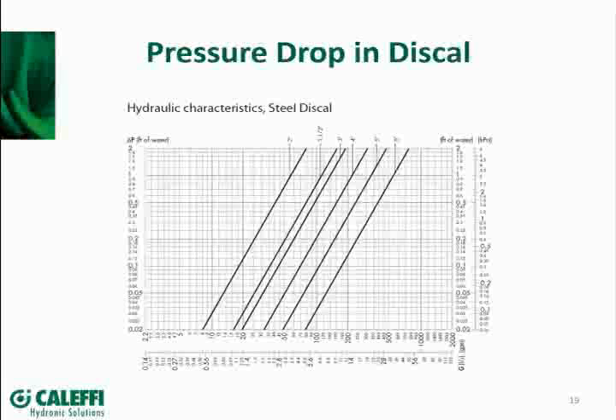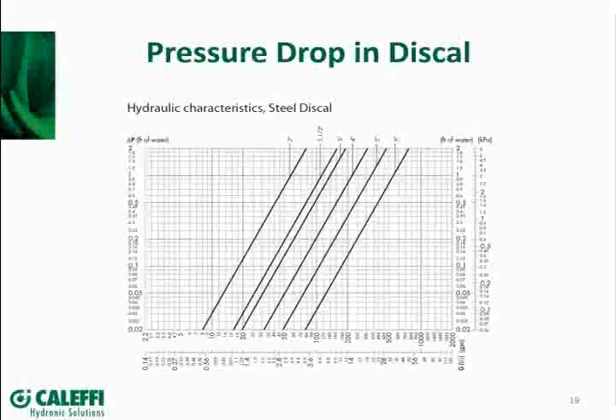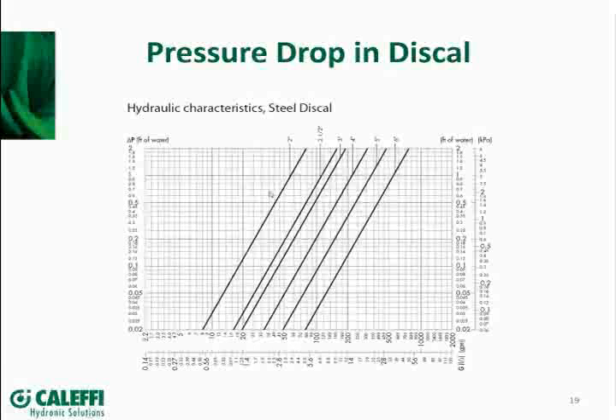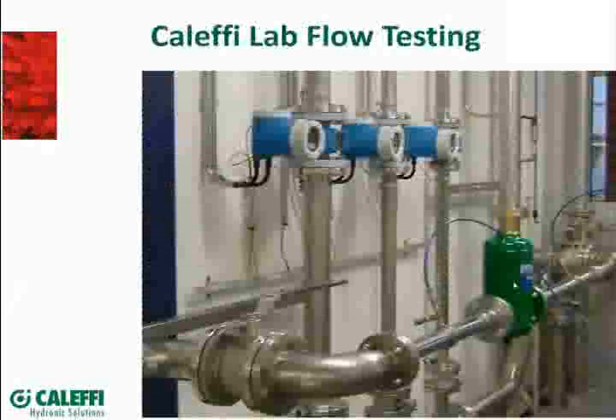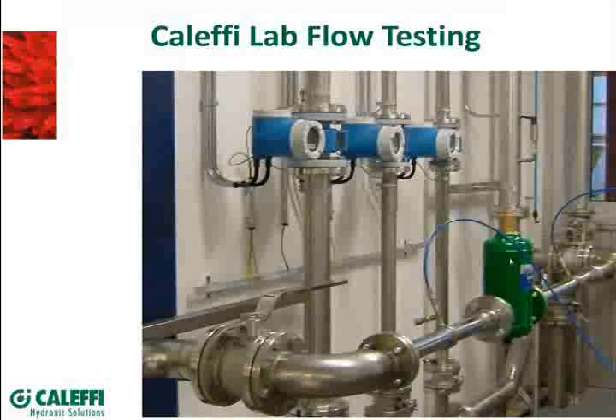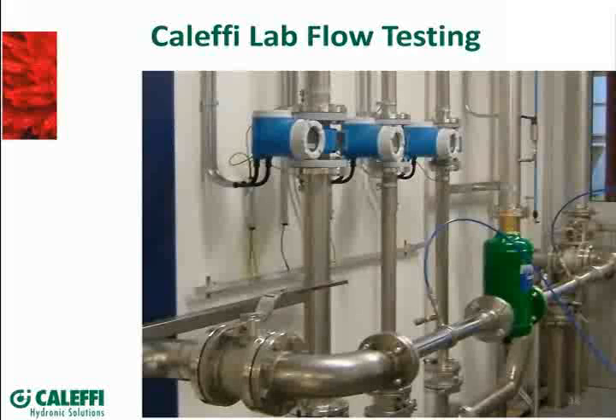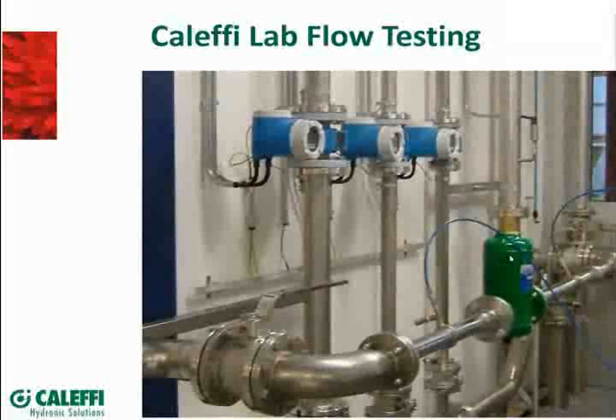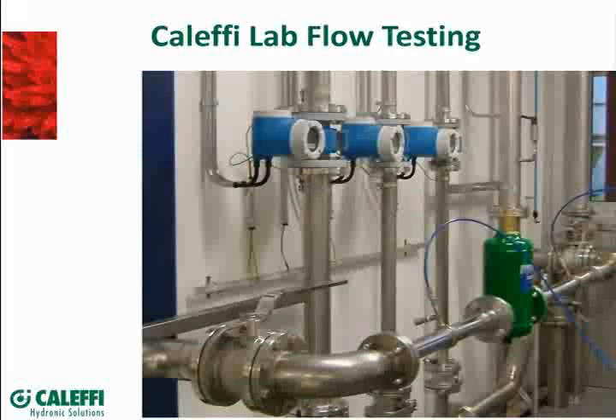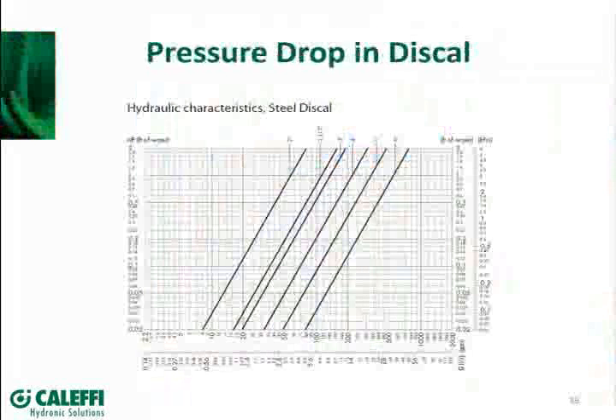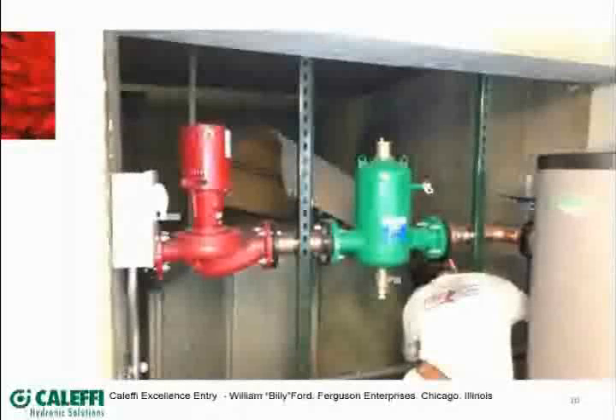We test everything we build on this bench and get our CV rating. When you buy one of our components — for example that disc-type air separator — here's the data sheet that's on the website and in our technical information. It shows both metric and U.S. units. You pick a flow rate on the bottom axis, run up the line, and see what the pressure drop is through that device at different flow rates. We design these for a typical 2 to 4 feet per second flow rate for a noise-free, trouble-free hydronic system, but we test our devices all the way out to 10 feet per second and still get excellent performance.